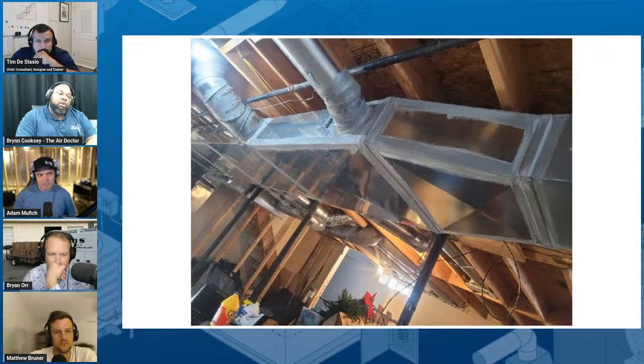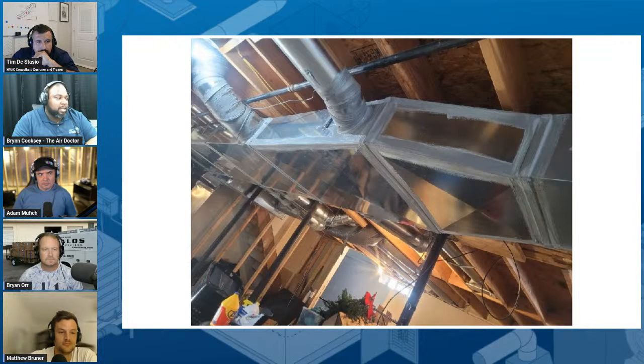It depends. If the load is so far out of the way, usually a major duct mod is required. In this situation, we had to pull all the ducts down and start from scratch. Sometimes, after we properly size the equipment, the ductwork is now properly sized. It happens. In that situation, we do a small duct mod. Maybe we'll move some supplies to different spots and make sure it's balanced correctly. So it depends on the situation.